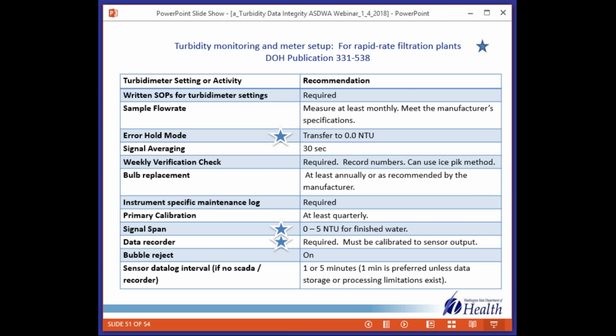The error mode is a really important thing. If you have any controllers that have this setting, make sure you know how they're set. Make sure they're not holding the last good reading. And last on the top 4 is you have to have written SOPs for your turbidimeter settings, so all the staff know what they are and you can replicate that.